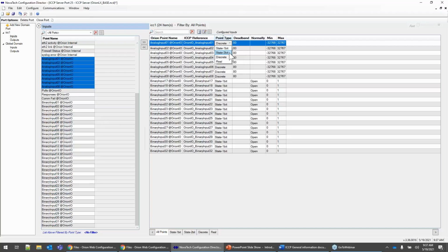The best typical example is if we use some logic within the Orion and we want to create some of these points. The best field use case would be monitoring a switch, where the 2 different bits are represented by the 52A and the 52B contact, meaning you can monitor to see if a switch is actually closed or open by each of those points, or if the switch is actually in motion during a transition from a commanded close or trip. If you're reading a 00, that would mean the arm is still in transition between the 2 states. So you can use it for monitoring that.